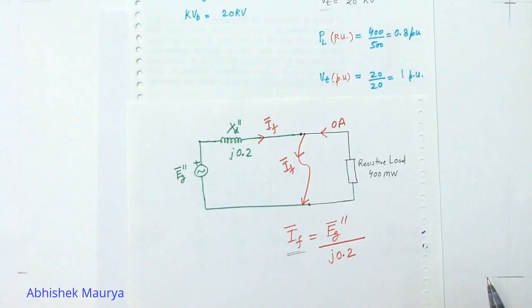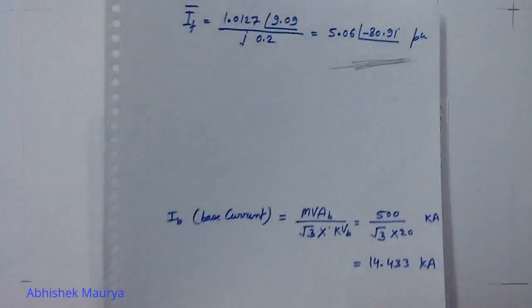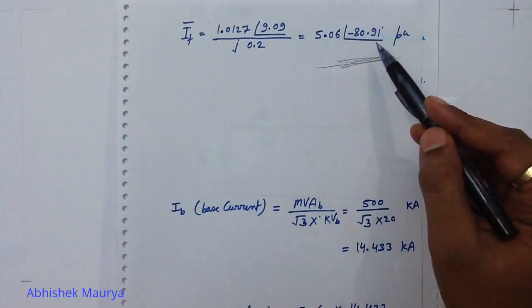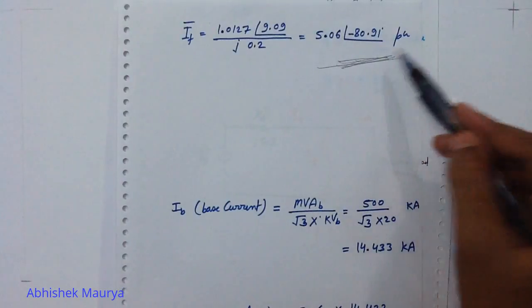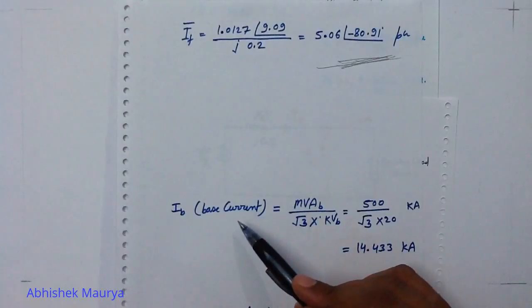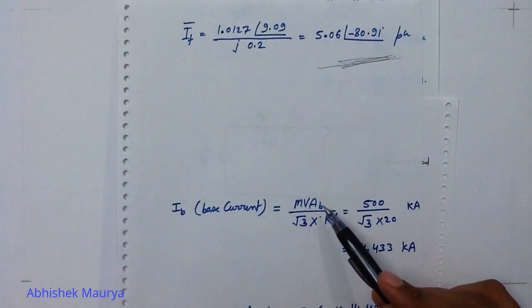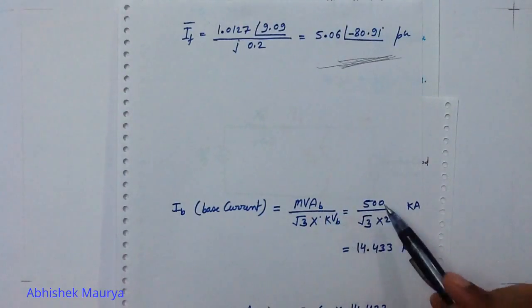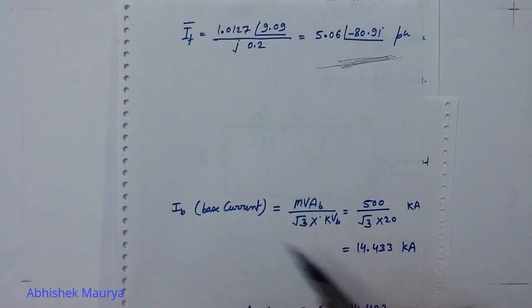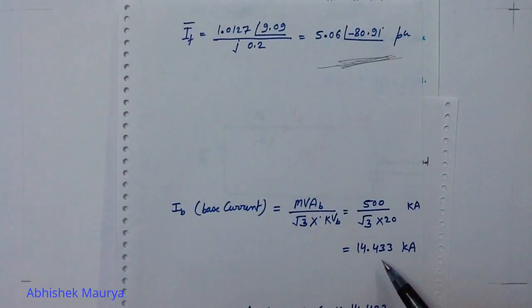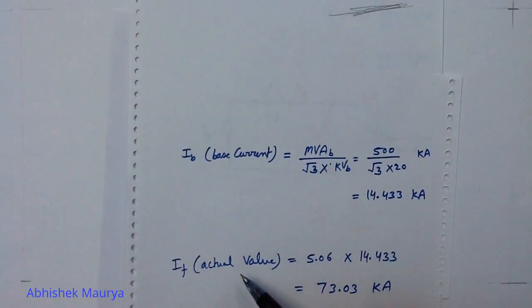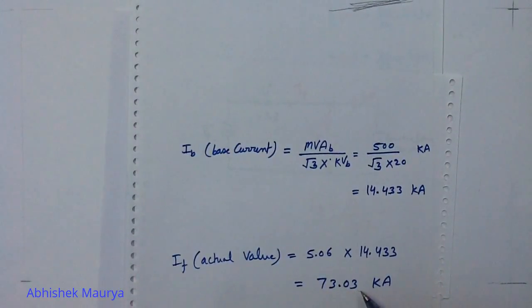Step 3: Calculate the fault current. Fault current IF equals Eg double-dash upon J0.2. After calculation you get 5.06 angle −80.91 degrees per unit. If the examiner asks for the actual fault current, calculate the base current: base current equals base power divided by (√3 × base voltage) = 500 MVA / (√3 × 20 kV) = 14.433 kilo-ampere. The actual fault current is then 73.03 kilo-ampere.